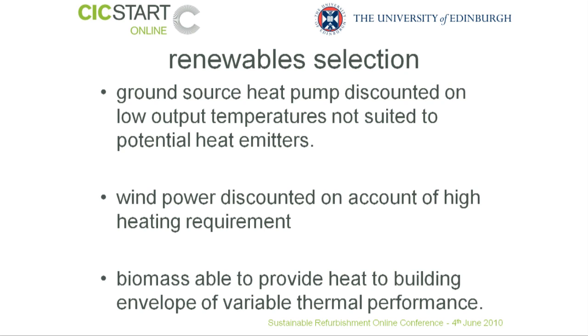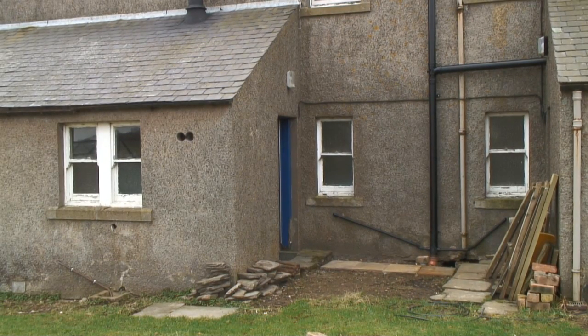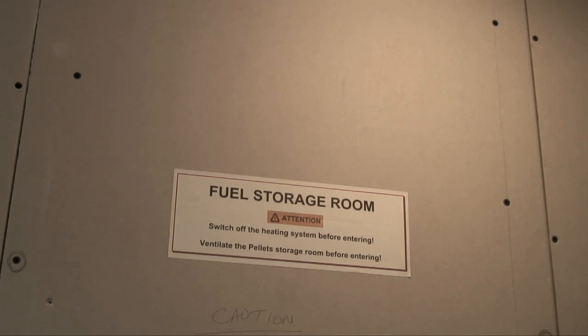There was space for the biomass installation to go in, but there was a major challenge in how we intended to deal with the existing listed building. The biomass installation for the cottage cluster is located in one of the outhouses, originally used as a small kitchen. There are three key components to the system. We have a boiler room accessed directly from the outside. Within it, we've specified and put in an Ökofen boiler rated at 32 kilowatts. Here you can see the Ökofen wood pellet boiler with its attendance service mechanism taking wood pellets from the store next door.